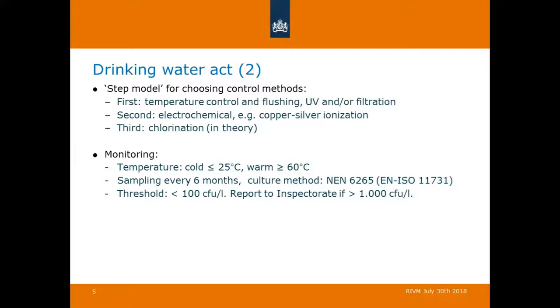You have to use the culture method, the Dutch culture method NEN 6265, and also recently we updated, and you now have the international standard that can also be used. Next year it will only be the international standard 11731. The threshold is less than 100 colony forming units per liter, and if you're above 100, you have to take action and lower your concentration.